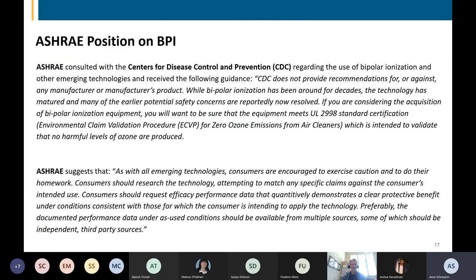ASHRAE's position on BPI is simply that they consulted with the Centers for Disease Control and Prevention. And while the CDC does not provide recommendations for or against any manufacturer or any manufacturer's product, not only bipolar ionization, but others, they noted that bipolar ionization has been around for decades. The technology has matured and many of the earlier potential safety concerns, mostly ozone, are reportedly now resolved.